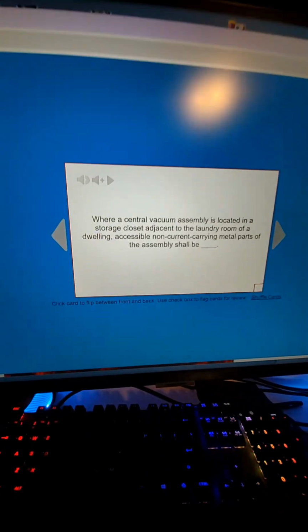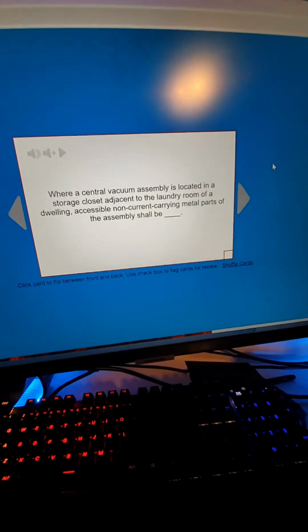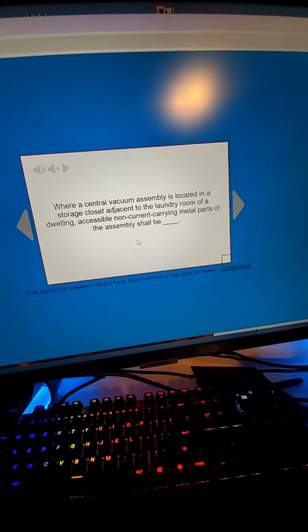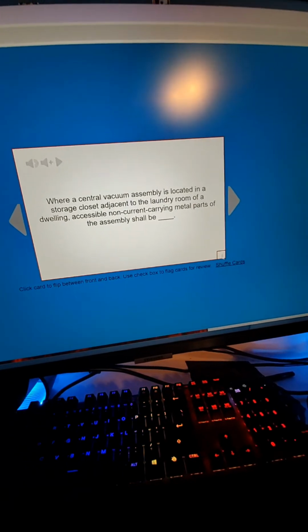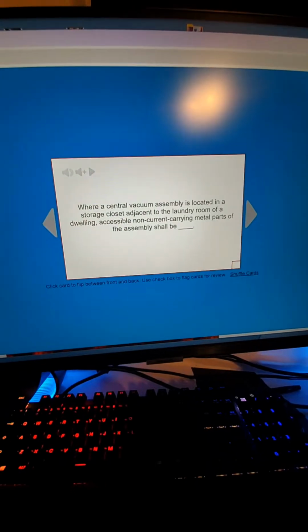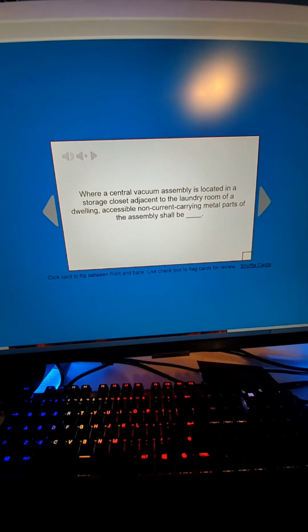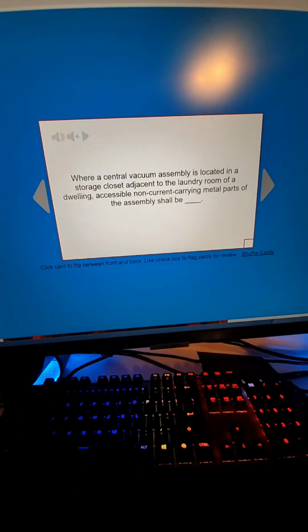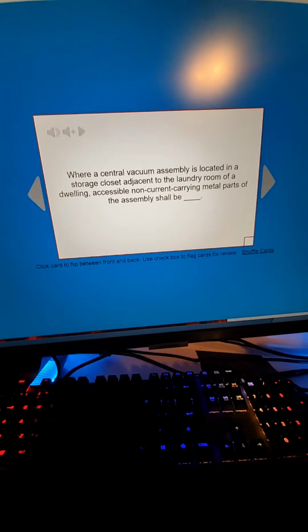Let's not click on that and try to highlight. We can't highlight, so that's kind of irritating. I thought we had to push the next button. I didn't know that we could. I thought we had to push down here. Where central vacuum assemblies is installed in a storage closet adjacent to a laundry room of a dwelling, accessible non-current carrying metal parts of the assembly shall be bonded. But let's look at it.